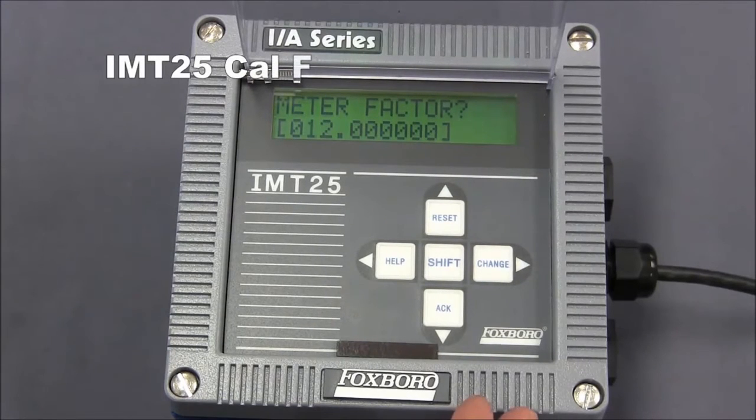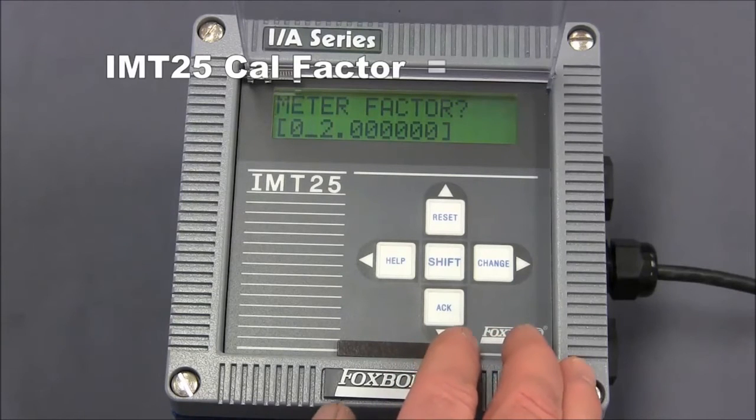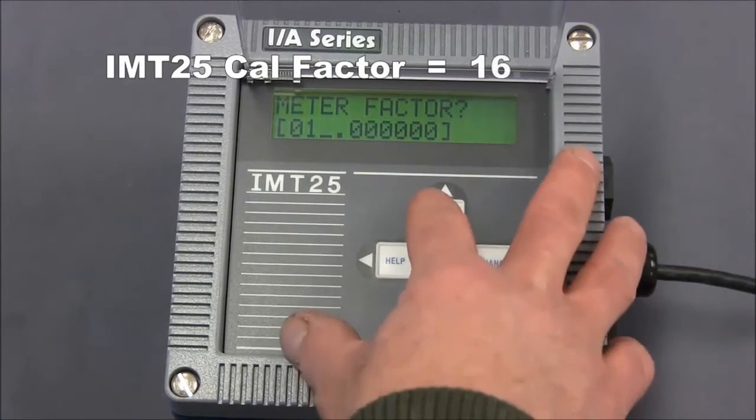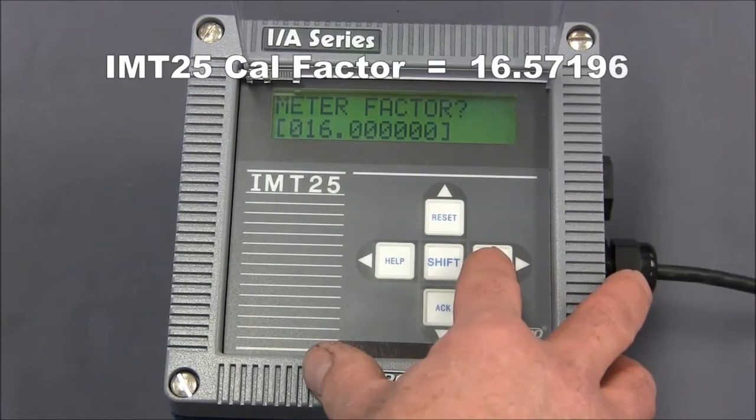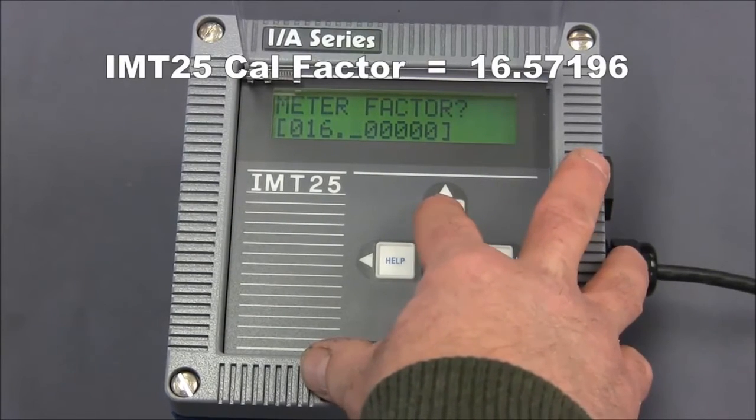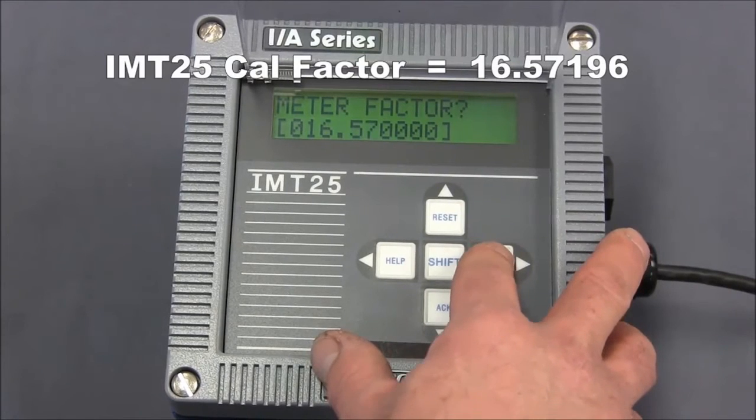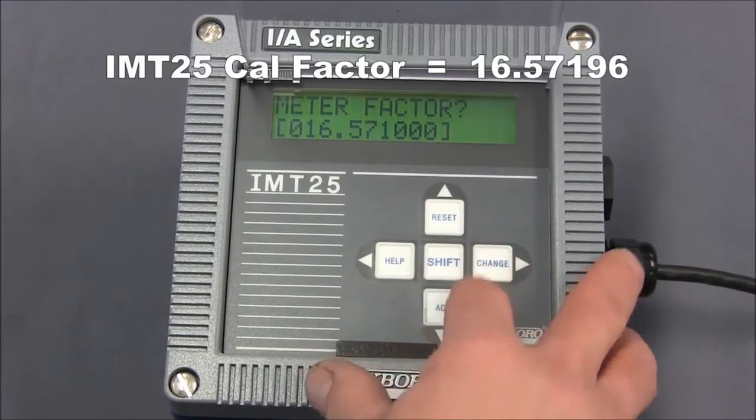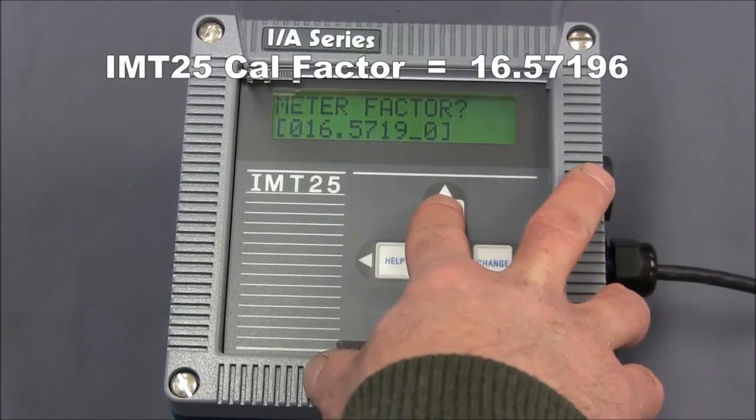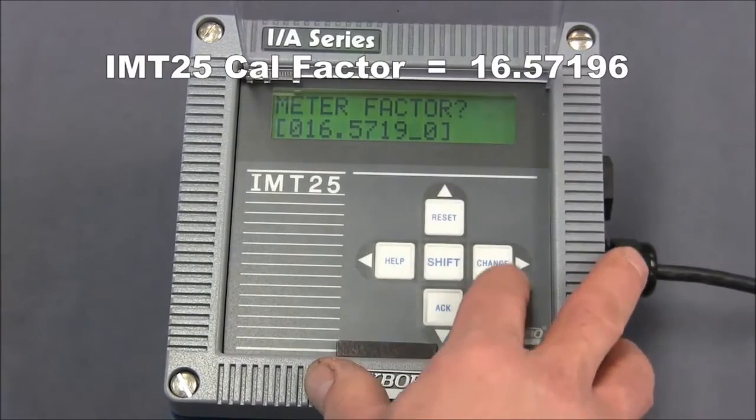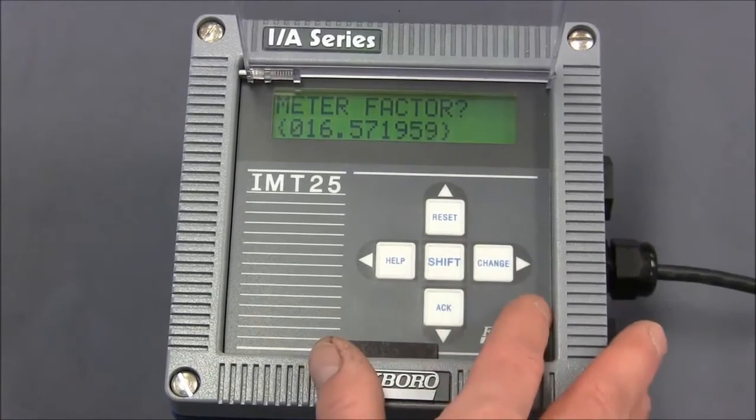Once the transmitter is in edit mode by the left bracket flashing, you would now use the right arrow key or the change key to move along to each of the different digits and change it to the meter factor that's actually stamped onto your flow tube's data plate. In this case, the IMT25 calibration factor is 16.57196. So we'll move along and change this to 16, using the up and down arrow keys to change the numbers and the right arrow key to get to the different digits. We hit the right arrow again to get the right bracket flashing, and then finally we hit the right arrow one more time to lock that number in.